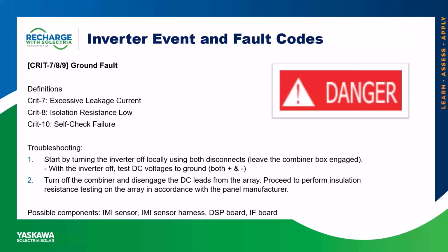As for recommended troubleshooting, we would ask you to start by turning the inverter off locally using both disconnects. Leave the combiner box engaged, and then proceed to test DC voltages to ground, both positive and negative. Now for non-DCG XGI inverters, the array is considered floating, so the longer you hold a reference to ground from either positive or negative, the voltages should proceed to bleed out towards 0.